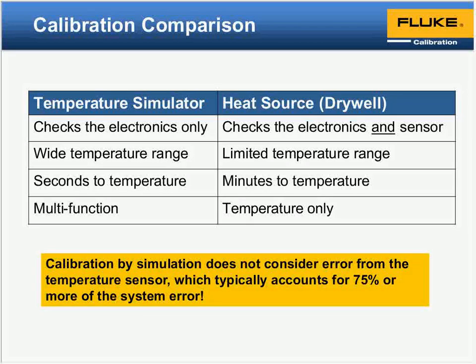things like that. Going kind of to the other end of the spectrum here, where you're actually using a heat source and you've got the sensor and the electronics put together, there are some things to consider that kind of limit the speed. Basically, you've got to wait for the stabilization time, heat up and cool down of the heat source. So maybe minutes or possibly hours to do the testing versus a simulation where you are doing it almost instantaneously once you program the unit and tell it to simulate. And to the temperature side too, with the heat source, you're only looking at a heat source. So again, there are some things as far as the electronics side. So again, the big takeaway here in that yellow box is that when you're simulating, you're really not getting a good view of the entire picture, which is the sensor piece. And sometimes, depending upon what you're doing, that sensor error can account for up to 75% of the error in the system.